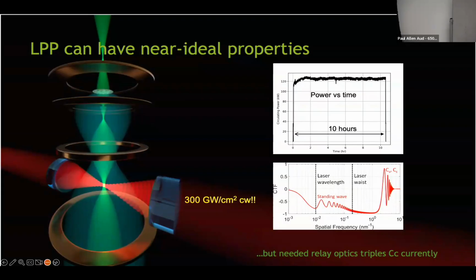We use that extra lens to our advantage. It magnifies the diffraction pattern about 5-fold, giving us an opportunity to improve the match of the laser beam diameter to the diameter of the undiffracted part of the electron beam. So it's very hard to focus the laser beam to the size of the electron beam in the backfocal plane. And then there's another lens to turn the virtual image into a real image. The power can be stable for 10 hours until you want to go home and turn it off.